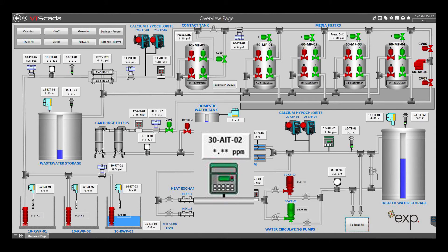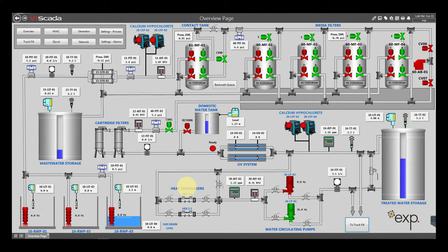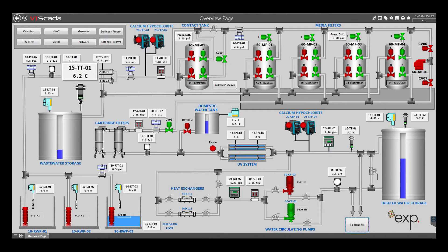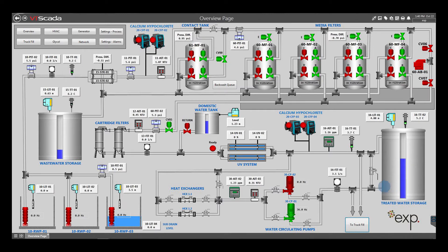To prevent freezing, the backwash and treated water tanks are heated by the boiler piping with heat exchangers. The backwash tank receives wastewater regularly, and the heat exchanger inside the tank keeps the water above 5 degrees Celsius. To prevent freezing inside the treated water tank, the circulation pumps move water continuously from the tank, through the heat exchangers located inside the building, and back to the tank.